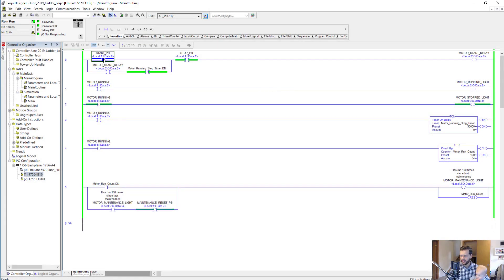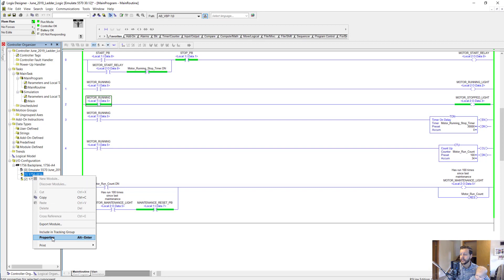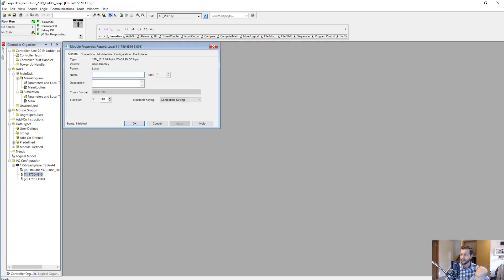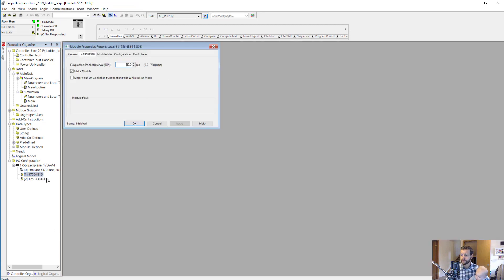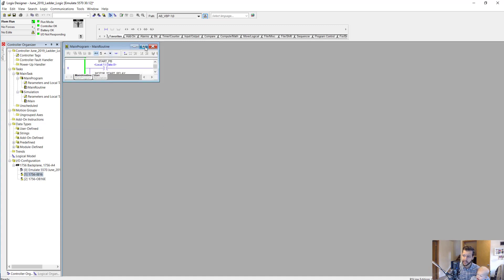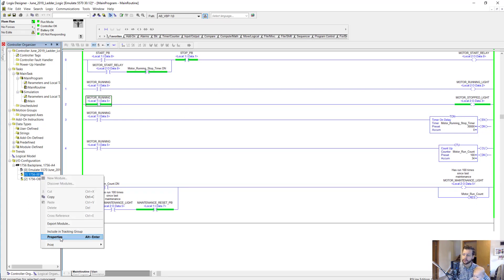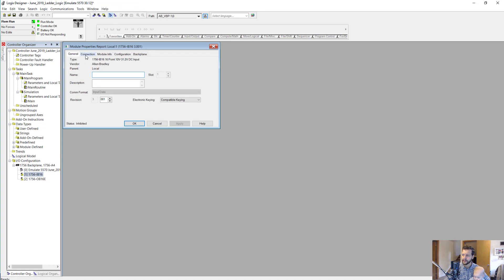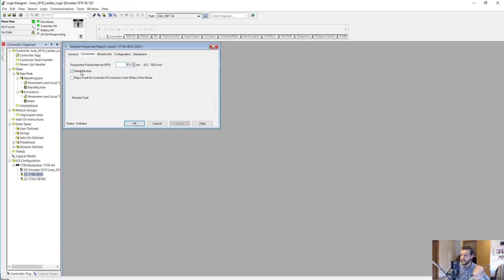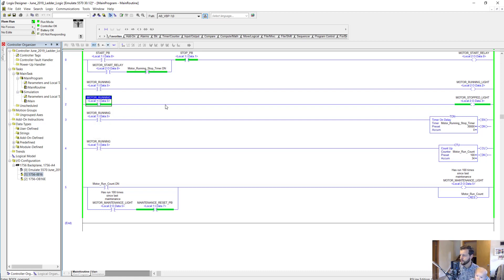Okay, so I realized that the motor start relay and motor running bits were toggling on and off super fast even though we couldn't see it. The reason is it was trying to read from this input module, and since there's nothing hooked up to the input module, it was reading a 0 and we're telling it to be a 1 in the simulation logic, so there was a conflict there. To solve that, I opened up the module properties for the input module and inhibited the module, and then it won't be trying to overwrite. So there's a little tip for you, bonus tip.